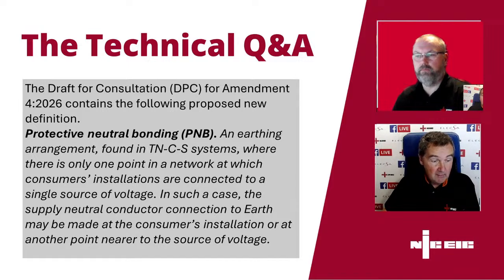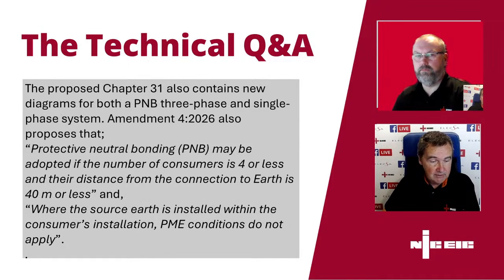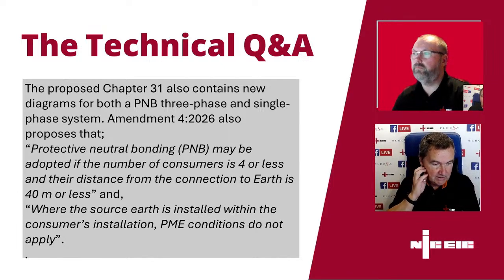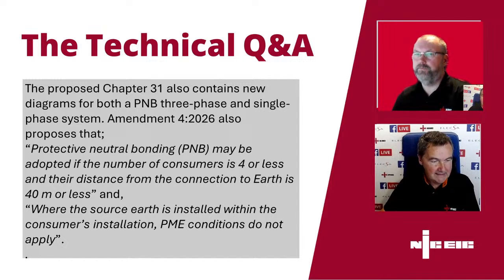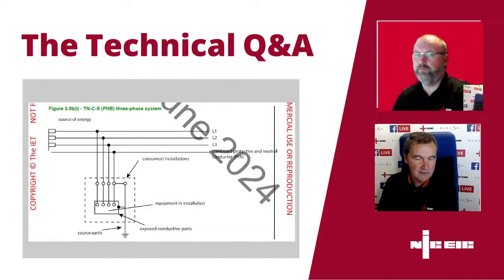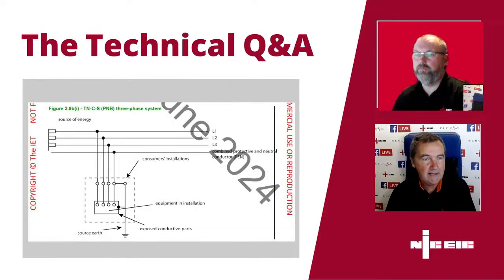The new proposals in Amendment 4, when they go into Chapter 31 on earthing arrangements, also tell us that PNB may be adopted if the number of consumers is 4 or less, and their distance from the connection to earth is 40 metres or less. It makes clear that where the source earth is installed within the consumer's installation, PME conditions do not apply. That's the clear difference - it's not the PME version of TNCS that people are familiar with.